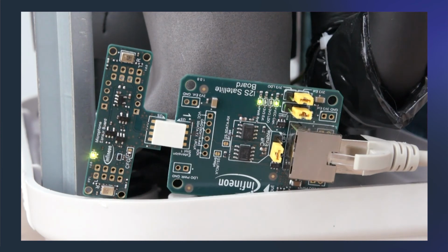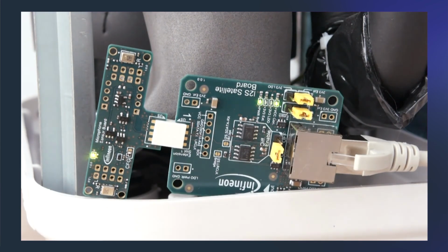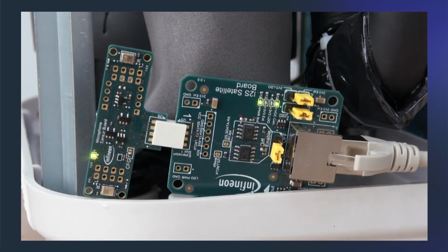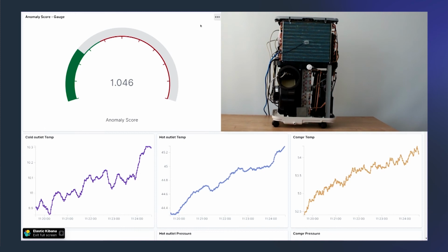Okay, let's move on. Here you can see the microphone. It is a high dynamic range microphone that is used to record sound inside the HVAC body. The sound spectrum analysis helps to detect many failures before the HVAC stops working. It should be noted that unfortunately the usage of microphones inside the device could be prohibited. Let's move to the demo.